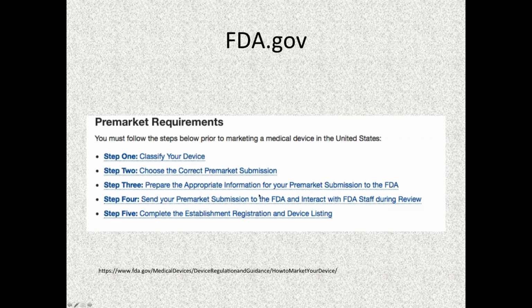So this slide was taken from the FDA.gov site. Step 1 is to classify your device. Choose the correct premarket submission. That's either 1, 2, or 3. And in the case of a 1, you don't have a premarket submission. You only have a 510(k) or you have a PMA. Prepare the appropriate information for the FDA, and there are guidance documents for those, and send it to the FDA and interact with the FDA staff during the review. And today they've actually allowed us to do what's called a pre-submission to make sure that the evidence you're going to provide is adequate. It takes a little bit more time, so if you don't have the time, you might want to just consider following the guidance document to the letter of what the guidance says, and then send that in, and then complete the establishment registration and device listing.